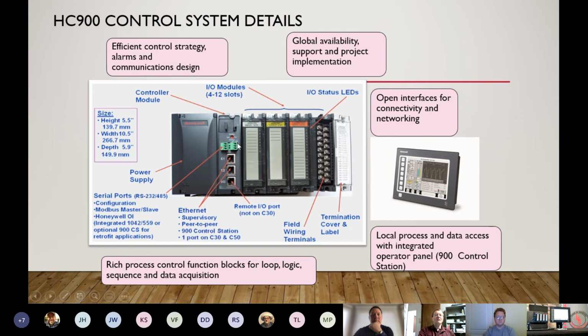To the right of the CPU, we have our first slot, slot 1. In the HC900 world, we have several different size CPU racks or I/O racks. We have a 4-slot, an 8-slot, and a 12-slot chassis. So again, based on how many I/O you'll need, you'll choose the rack to accommodate the amount of I/O.